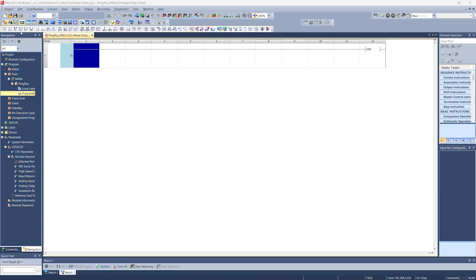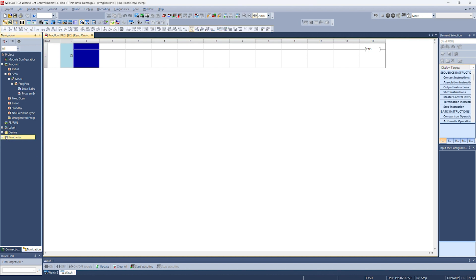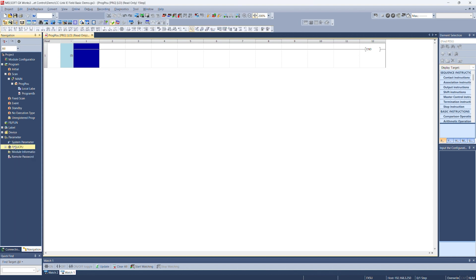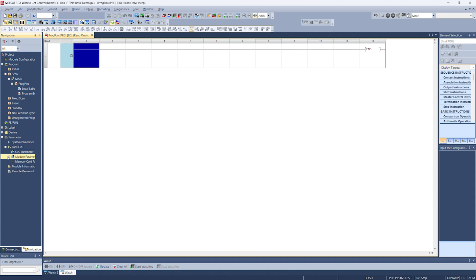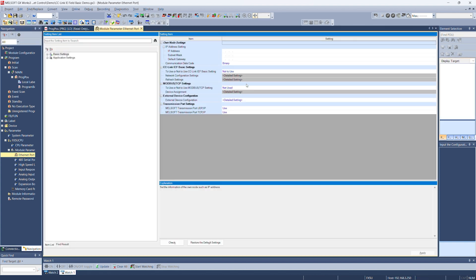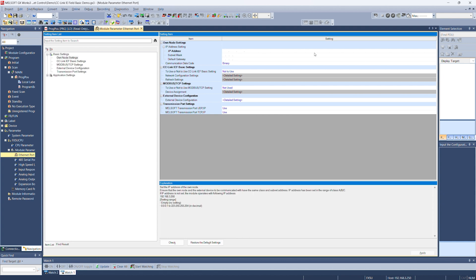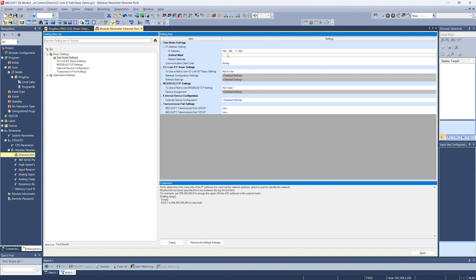All I want to do is open up Melsoft GXworks 3 and start a new project. In our new project, we'll open up parameter, open up FX5U CPU, and open up module parameter, looking for Ethernet port. Let's set up the IP address of our FX5U CPU. We're going to use the default 192.168.3.250. And the subnet mask we'll leave at 255.255.255.0.